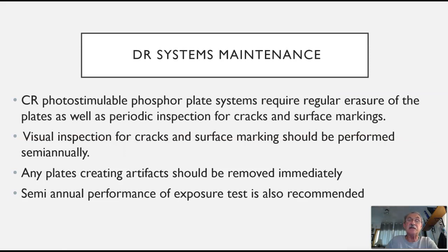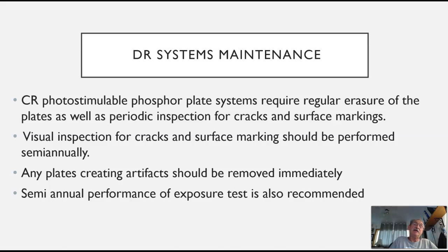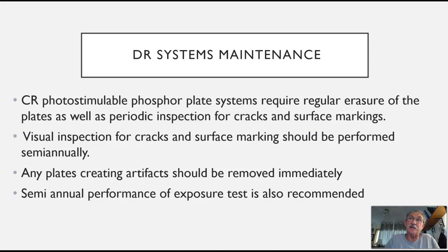DR system maintenance: computed radiography photostimulable phosphor plates require regular erasure of the plates, as well as periodic inspection for cracks and surface markings. We want to take them periodically out of the cassette and give them a good going over. We're going to visually inspect for cracks — surface marking inspection should be performed semi-annually, about every six months. Any plates creating artifacts should be removed immediately, and a semi-annual performance of exposure testing is also recommended, typically done by the quality control technologist.